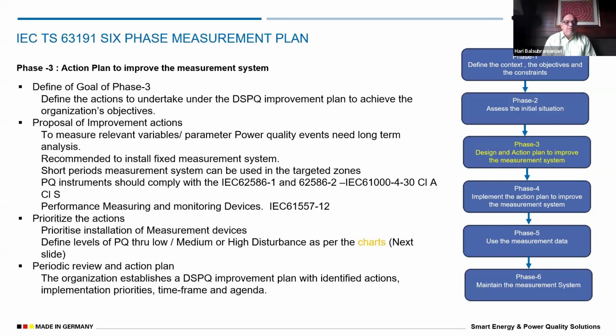What is the proposal for improvement action? Probably what we can do is target specific zones - this is the zone I wanted to start with, and fix certain kinds of PQI meters in these zones. These application loads require more attention because I have more variable frequency drives in this particular application or use case. I will install better meters in these places rather than PMD products - I will use PQI instead. So we have to choose accordingly for various zones and applications, and then try to improve the monitoring system from level A to level B, or level 0 to level 1.